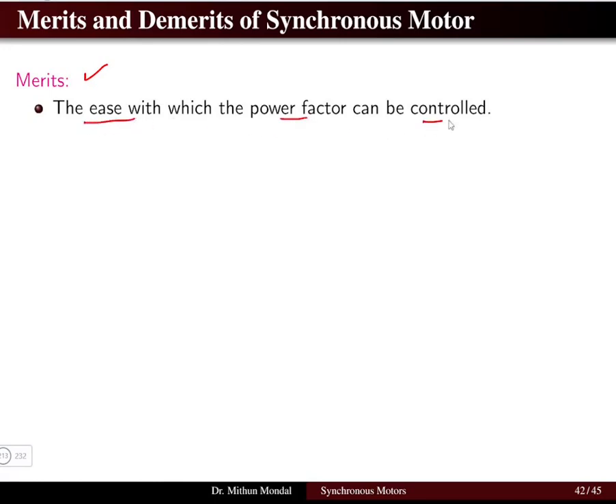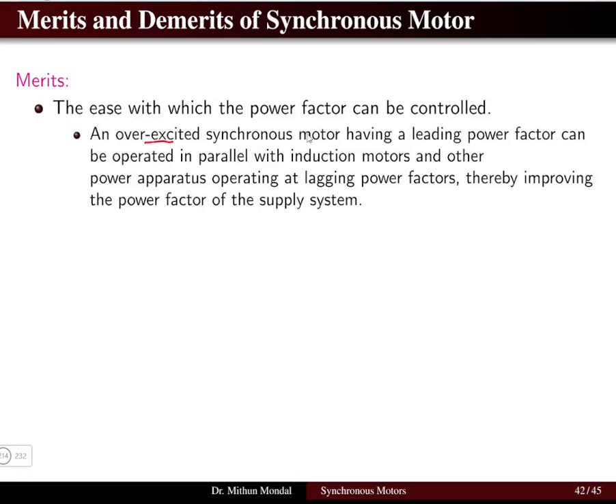The first merit of the synchronous motor is the ease with which the power factor can be controlled. We have seen in the previous lectures that the synchronous motor can operate in both the under-excited and overexcited cases. In an overexcited synchronous motor operating at a leading power factor, it can be operated in parallel with the induction motor, since in industries 95 percent of motors are induction motors which operate at a lagging power factor.